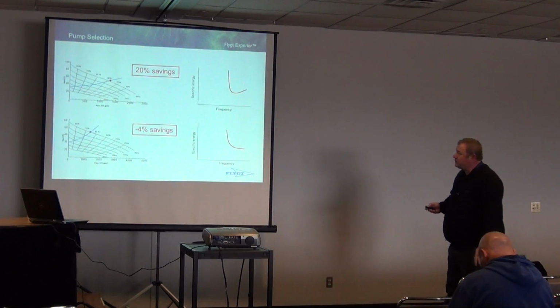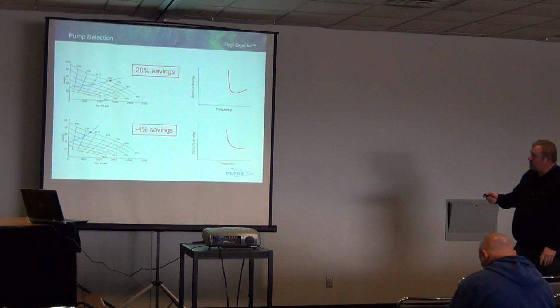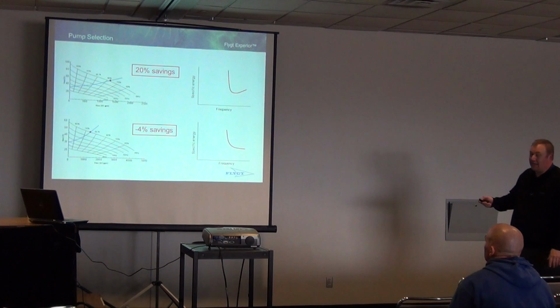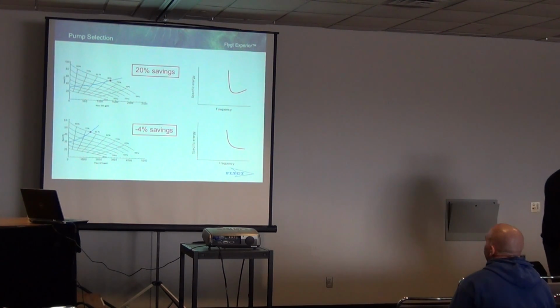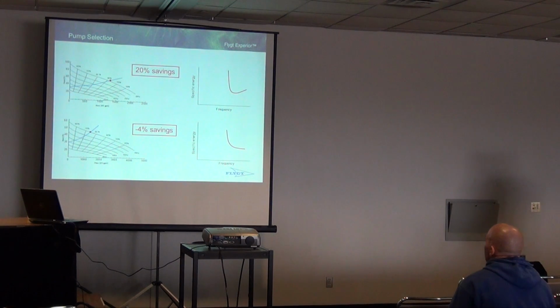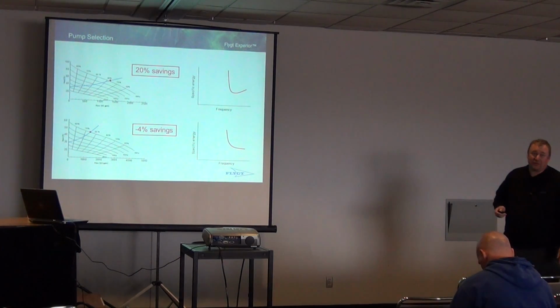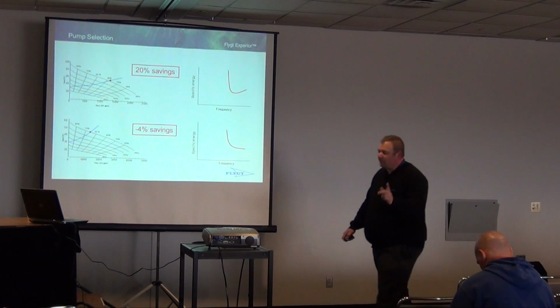Here are some more examples of curves. This is an example of a 20% savings in electrical costs by backing that speed down into the sweet spot of the pump. But if you have a system curve that lays poorly on that pump curve, you can actually lose savings by applying VFDs improperly. So a VFD isn't necessarily the end-all in saving energy. Again, it's great for starting things up, slowly ramping things up and easing that water hammer issue, but it is possible to lose money with them too if they're misapplied. So something to keep in mind.